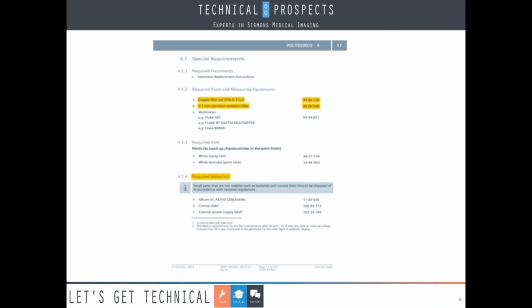Does Siemens issue updated PM procedures? From time to time, but I've had some that they didn't update for 7 years. It's really weird how they do that. We have a lot of them we haven't been able to update in the last few months, but they don't change too much. If they do anything, like at one point they changed the interval for replacing brushes on CTs — they went from every 6 months, which was excessive, to every year, or other intervals depending on it. But I don't know of any other changes. They do issue updates though, and you can call us if you have any questions. We have all this stuff.